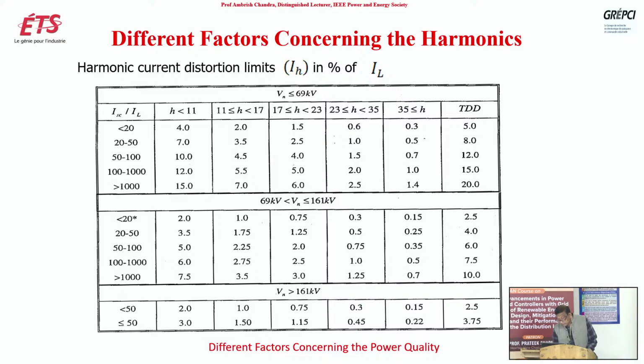For the voltage more than 161 kV, these are almost same. Here there is an error, this is 20 here. And these are almost same, not much change here. So this is IEEE standard 519, recently updated, but these are odd harmonic limits. But if you are having even harmonics, it will have more severe effect on the system. Even harmonics are not desired, not at all. So they have 25% limit. Whatever values you are having, calculate the 25% limit of that, and that is for even harmonics.